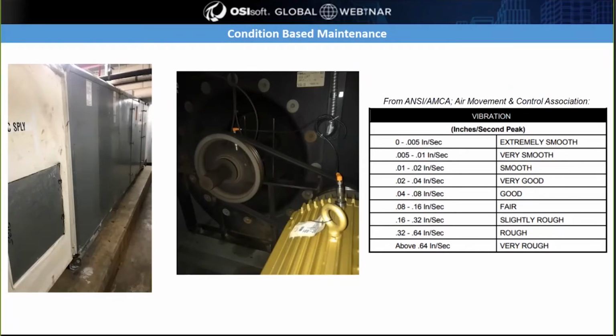And then on the right-hand side, we have the acceptable limits for vibration velocity. These come from a number of different sources. This here is from ANSI. You can also get it from ISO, and there are different organizations that have standards for vibration velocity limits in rotating machines. By monitoring the vibration signals and referencing these standards, we were able to create a spectrum of acceptable vibration velocities specific to this air handler.